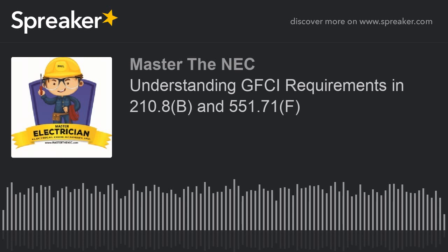So they didn't feel that the exposure was the same for 30 and 50 amp as it was for the 15 and 20, because typically the 30 amp or the 50 is what you'd get on a home that would be used in these recreational areas, but the 15 and 20 in those tent locations, for example, or some of the aspects that require those servicing type receptacles to be there for other things, are going to be cord and plug, and you're going to be plugging them in and out.